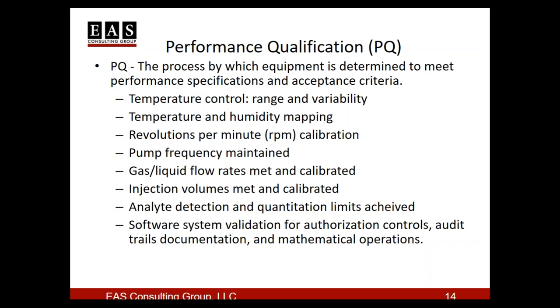If it's something that rotates, the RPMs may have to be determined and calibrated. Pump frequency—we need for HPLCs, you have to have a certain pump ratio for those things. And the gas flows, we need to make sure not only do they flow, but they flow at the appropriate rate. Injection volumes, to make sure that we're injecting the appropriate volume—if we're supposed to be injecting 5 microliters, or are we supposed to be injecting 10 milliliters? We need to make sure those are calibrated.